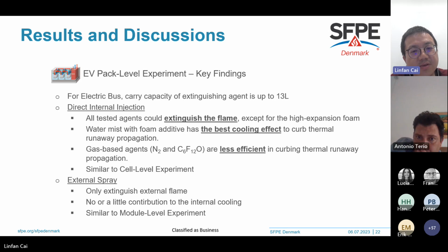Similar to the cell level and module level experiments, water mist with foam additive has the best cooling effect compared to other tested agents. Gas-based agents are least efficient at mitigating thermal runaway due to poorer cooling capacity, similar to the cell level findings. For external spray, it can only put out external flames, with little or no contribution to internal cooling, similar to the module level experiment.